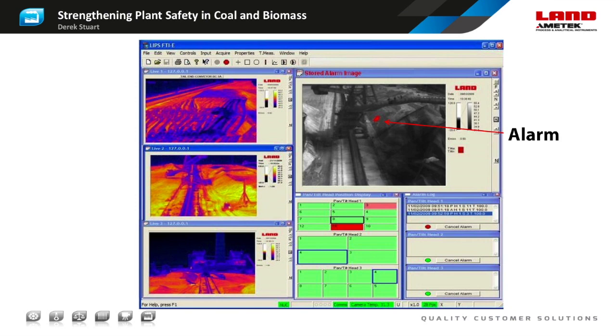Here's a display screen from a three-imager system. In the left-hand panel, we see the live thermal image from each camera, with the colour scheme chosen to give emphasis to the temperature range of interest. The upper panel is an image showing an area of high temperature highlighted. The bottom panel shows the patrol record for each of the imagers with the status of the designated zones. The upper camera has a total of 12 zones of interest, the middle one has four, and the lower has eight. For each zone, a green colour indicates no problem detected, pink shows that one pass found a problem, and red is an alarm condition triggered by three consecutive passes which found a temperature above threshold.